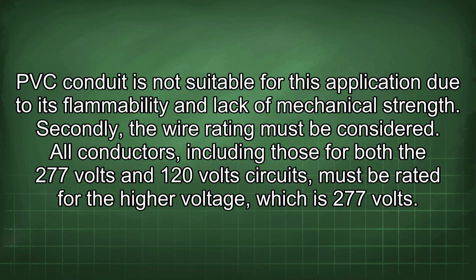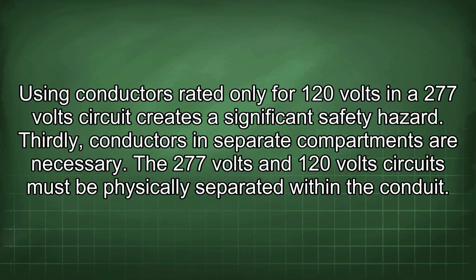Secondly, the wire rating must be considered. All conductors, including those for both the 277 volt and 120 volt circuits, must be rated for the higher voltage, which is 277 volts. Using conductors rated only for 120 volts in a 277 volt circuit creates a significant safety hazard. Thirdly, conductors in separate compartments are necessary.